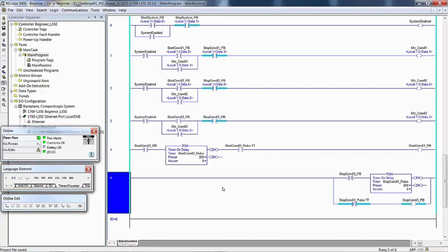Usually I'll call it green machine as is, and then I put in the date, and I might even put in the time, or I just put AM to show that I saved it in the morning when I got there. Then every time I make changes and save it, I give it a different name. That way, if I want to go back to what the customer had at the end of the day, in other words, I didn't get all my changes made, I can always download what they had to begin with, and it's right back to where it was.